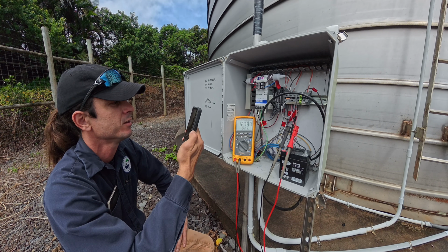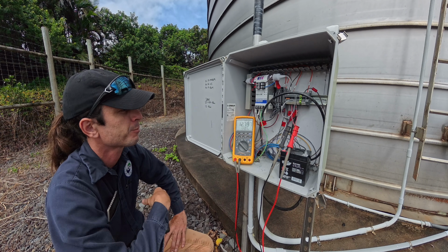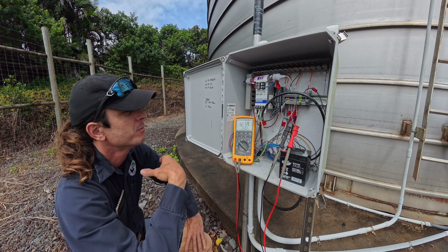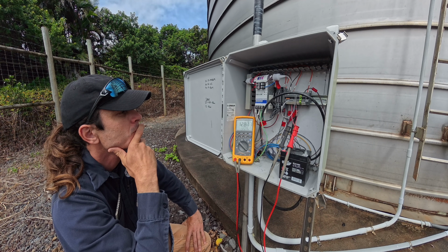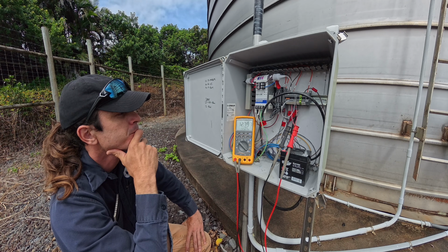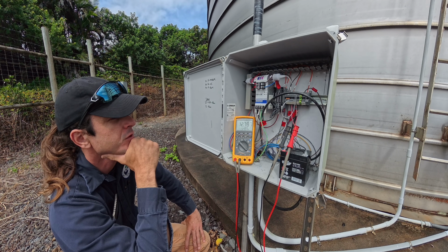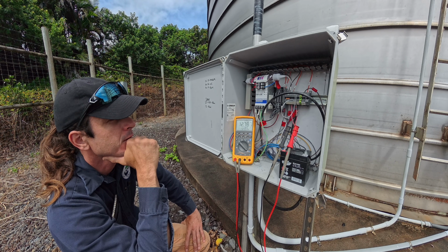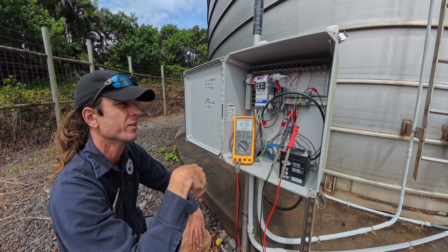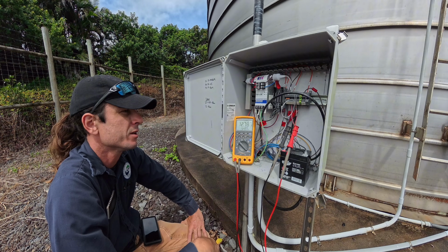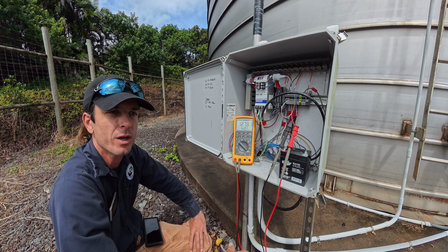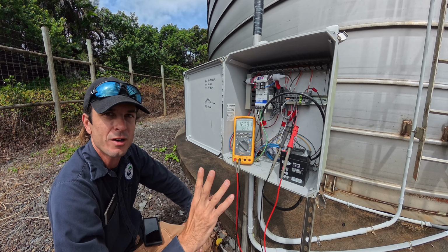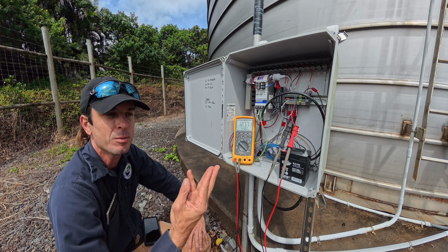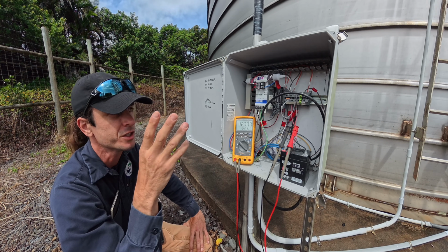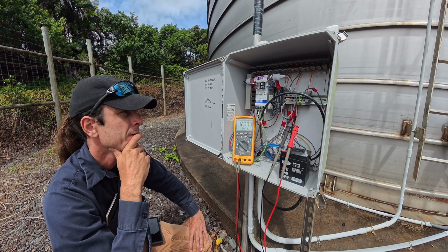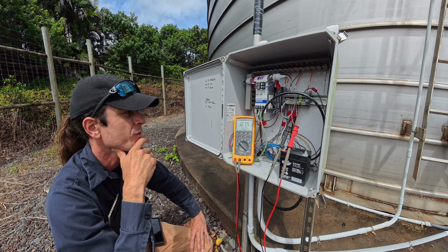And it's holding. Picture of that. Yeah, I think we're good. I don't know what could have blown that fuse. I should check continuity between this red and the ground, the shield, because I've seen that before, where between the two wires everything's healthy and fine, but the cable itself or somewhere else is shorted to the shield or to earth. That'd be unfortunate. So let's look at that.